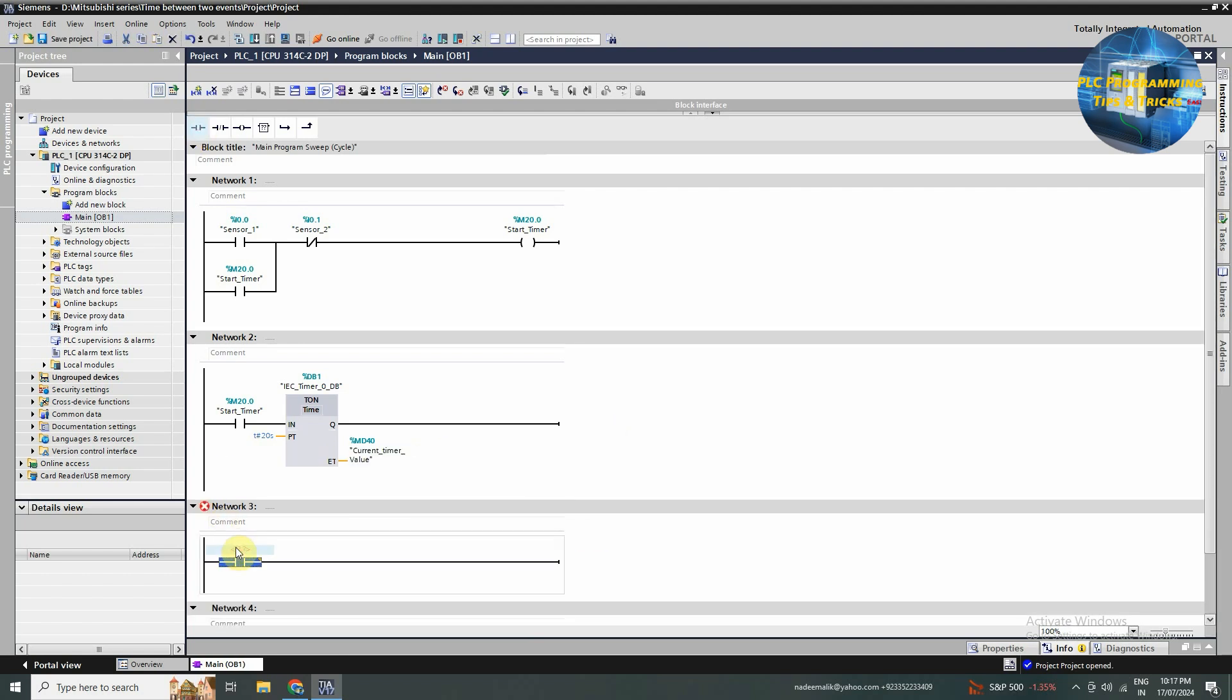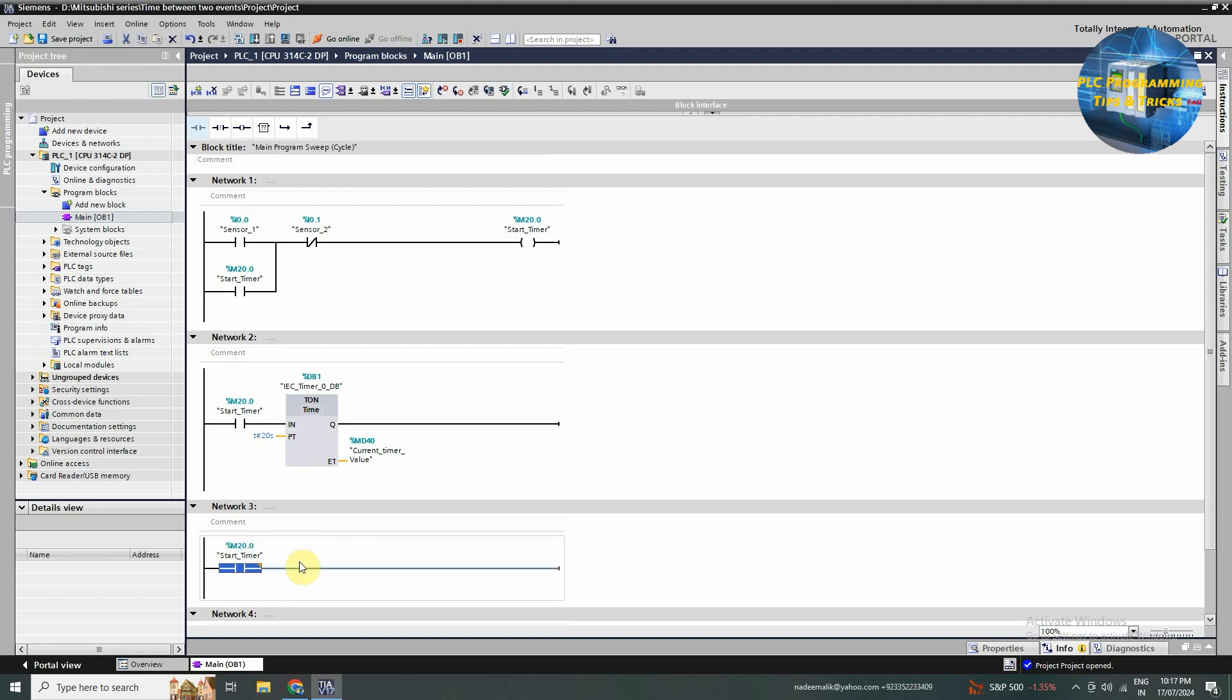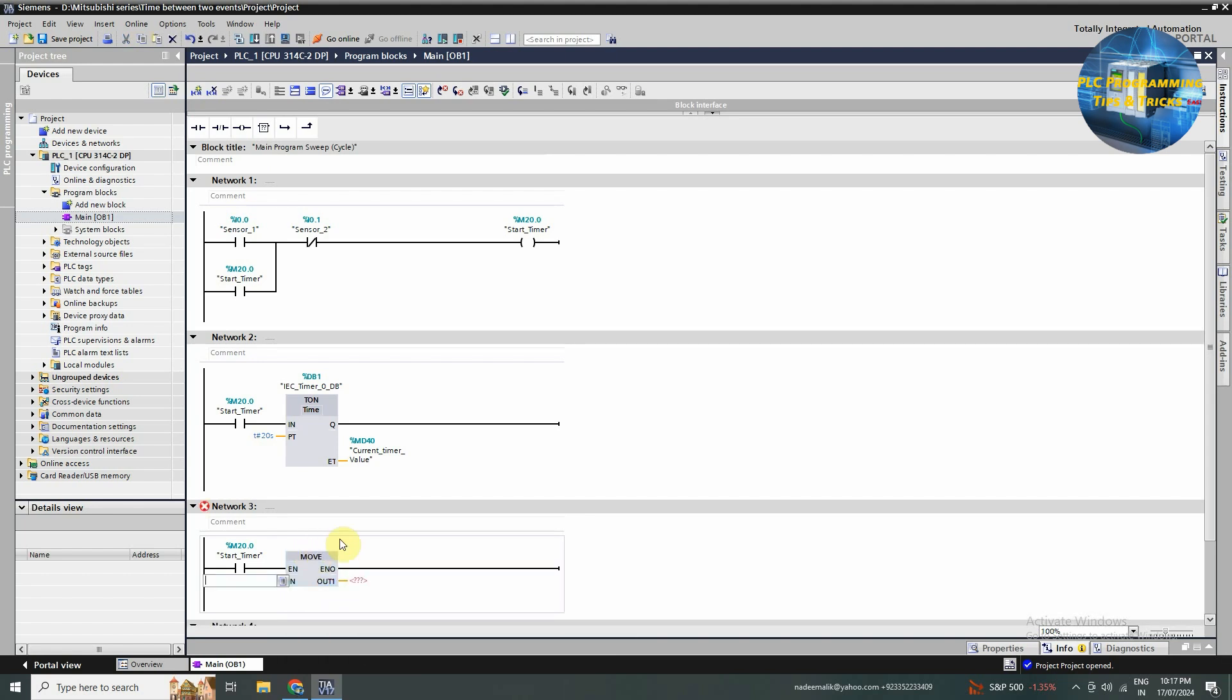In network 3, we will insert the start timer m20.0 bit. Next we will insert the move instruction. At the input of the move instruction we will assign MD40 memory which contains the current timer value.